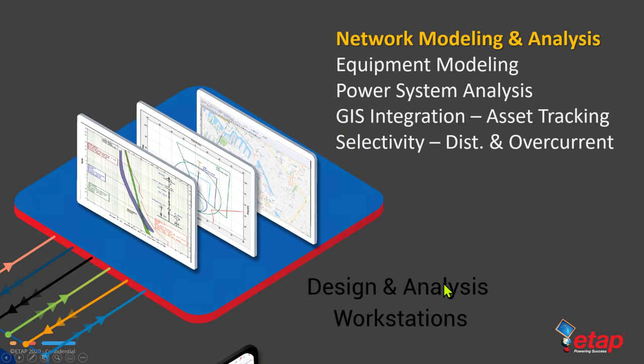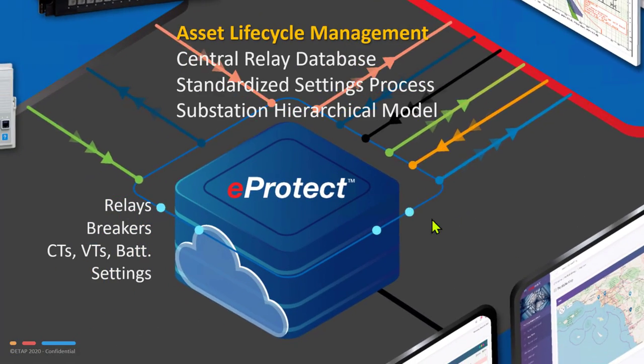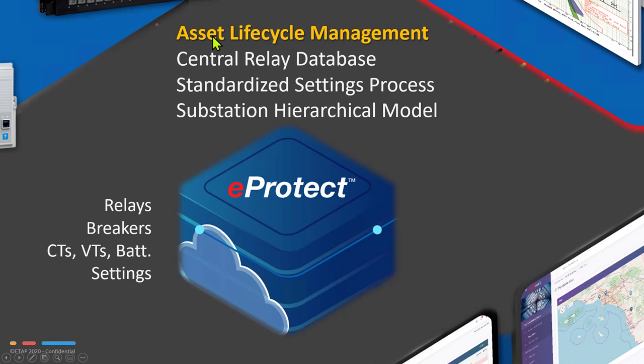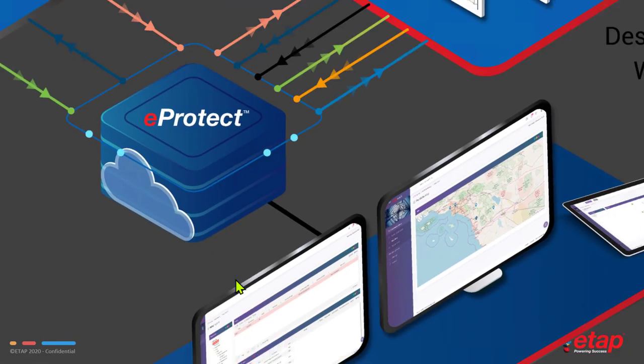The design and analysis workstations allow you to perform network modeling and analysis that includes equipment modeling and power system analysis. They include GIS integration with asset tracking, and of course host the popular ETAP Star and Star Z protection and analysis modules. The eProtect database itself performs asset lifecycle management by hosting the central relay database. It has standardized settings and processes, as well as a substation hierarchical model that hosts relays, breakers, CTs, VTs, batteries, and of course relay settings themselves.